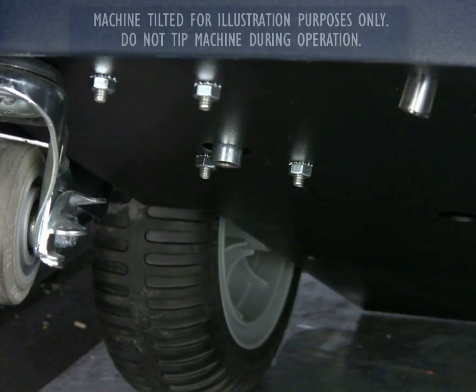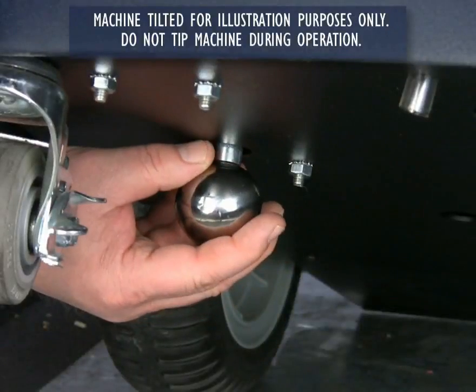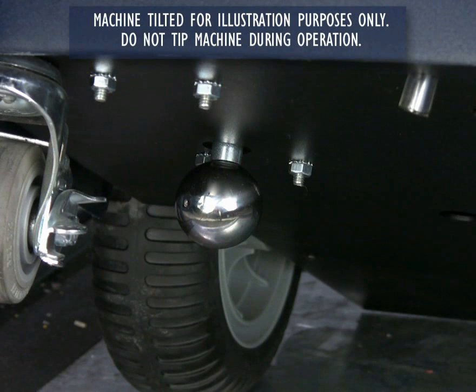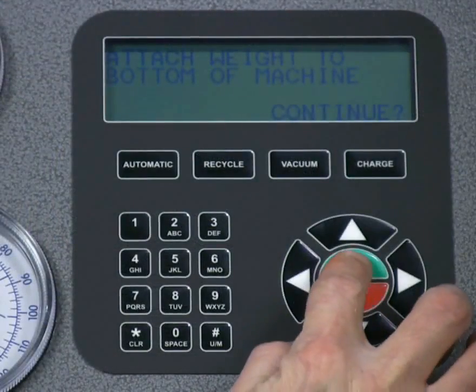As you can see here, there is a small magnetic post protruding from under the load cell platform. Make sure you affix the ball directly to this post. Be advised, we tilted the machine so you can readily see the magnetic post for illustration purposes only. Do not tilt the machine under any circumstances during this procedure. Now press the green Yes key to continue.